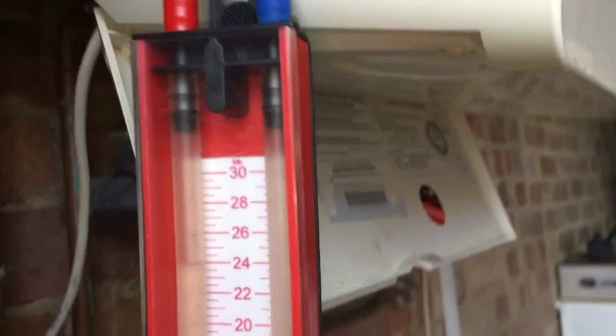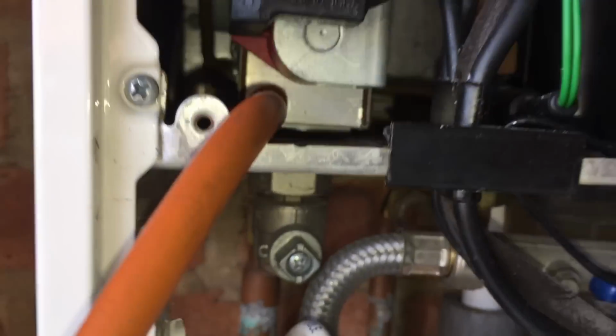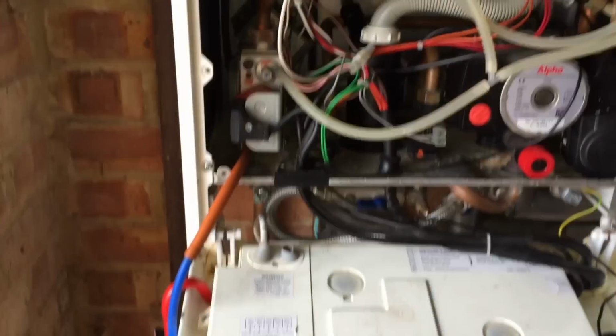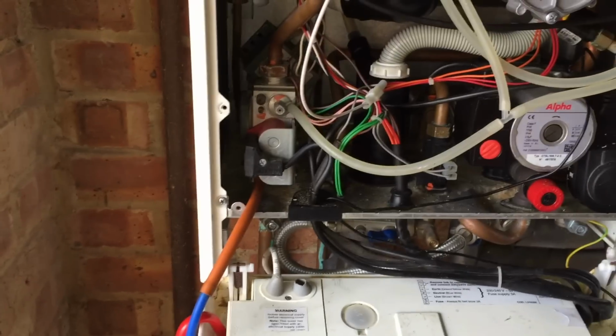So it's either going to be the outlet pressure of the meter is bad, or we've got all that debris in the bottom of the gas valve. So we might have to whip this gas valve out and try and clear all the debris out of it and out the gas pipes.